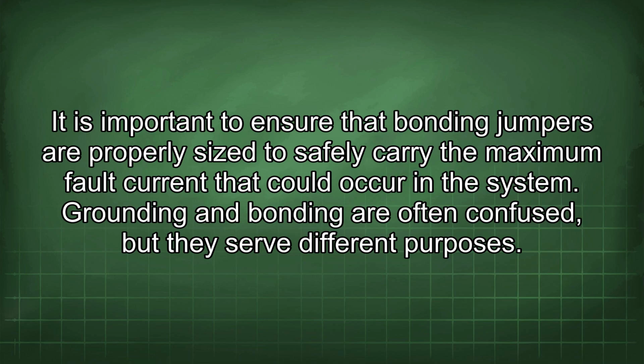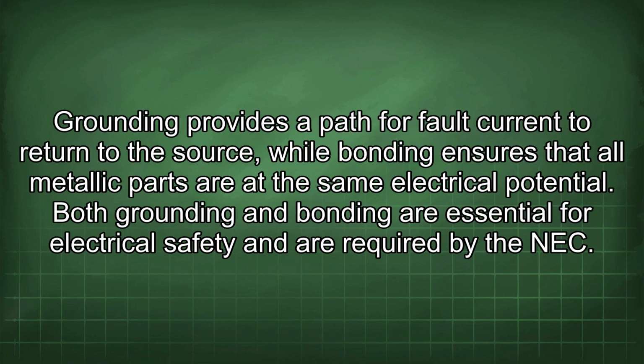occur in the system. Grounding and bonding are often confused, but they serve different purposes. Grounding provides a path for fault current to return to the source, while bonding ensures that all metallic parts are at the same electrical potential. Both grounding and bonding are essential for electrical safety and are required by the NEC.